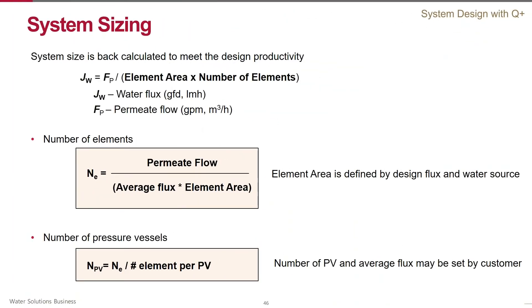Then you need to select the right type of membrane — you already know how to do that, as we talked about this previously. Once membrane selection is done, you need to properly size your system. These are straightforward guidelines: design capacity is used as a starting point, and following the design guidelines we can select the recommended system flux for a particular source water and back-calculate the required number of elements and pressure vessels.